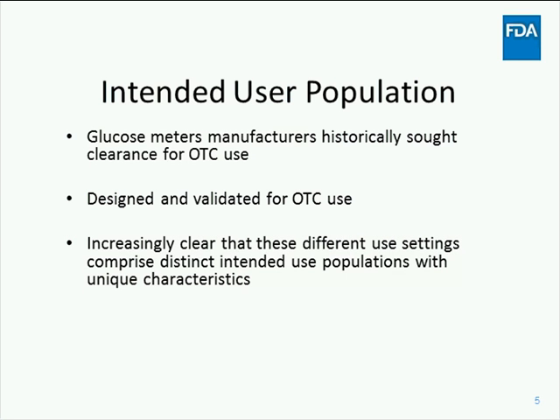For the majority of glucose meters, manufacturers have historically sought over-the-counter clearance, which has typically been done to obtain waiver for these devices so that they can be used in a variety of waived settings. In taking this approach, what has happened is that the majority of meters on the market today, including most of those that are used in professional healthcare settings, including hospitals, were designed and validated only for over-the-counter use. That means that healthcare professional use for these devices was not evaluated. It has become increasingly clear that these different use settings comprise distinct intended use populations with unique characteristics that should be considered during device design and validation.